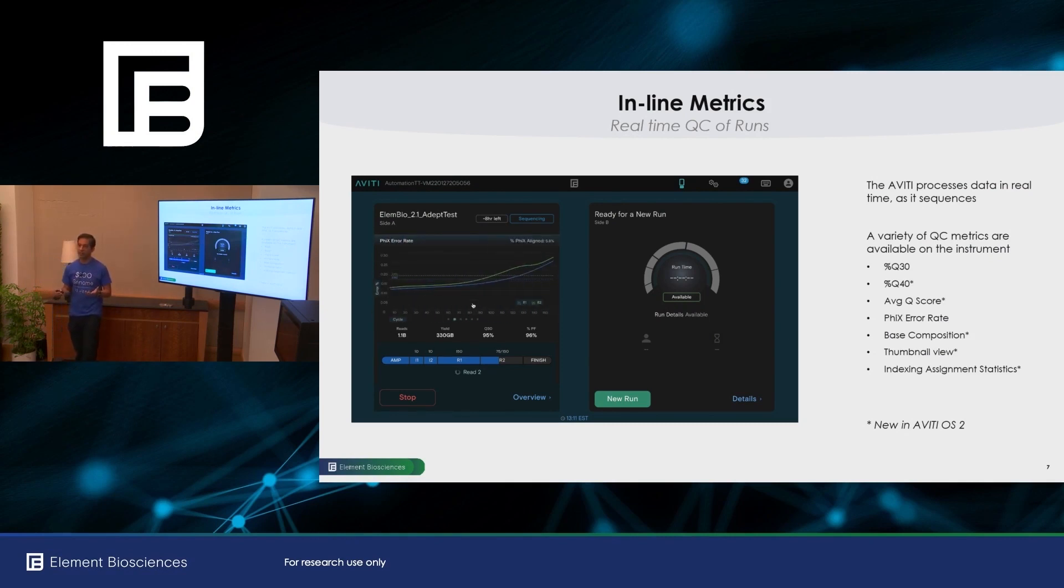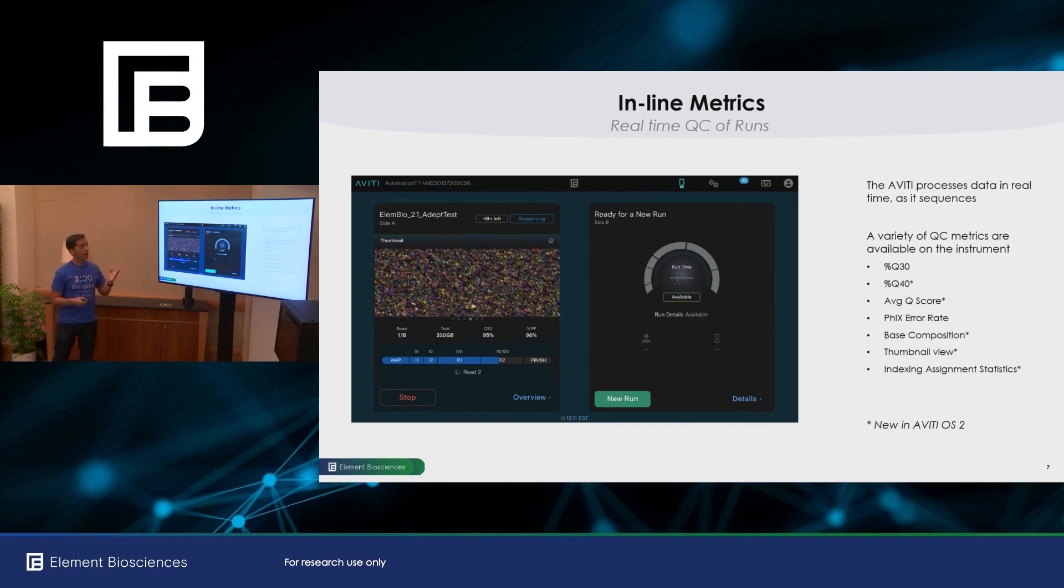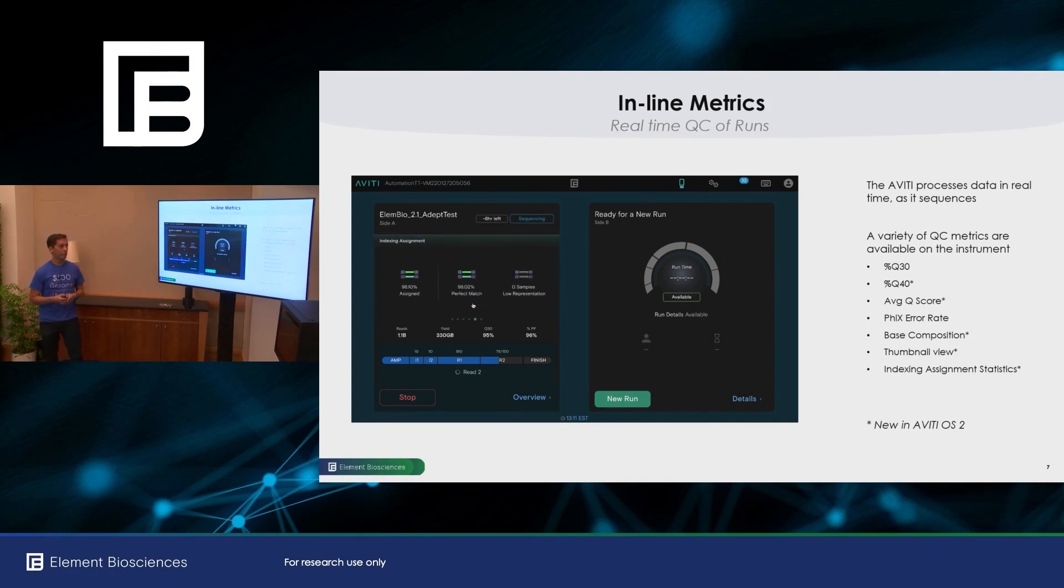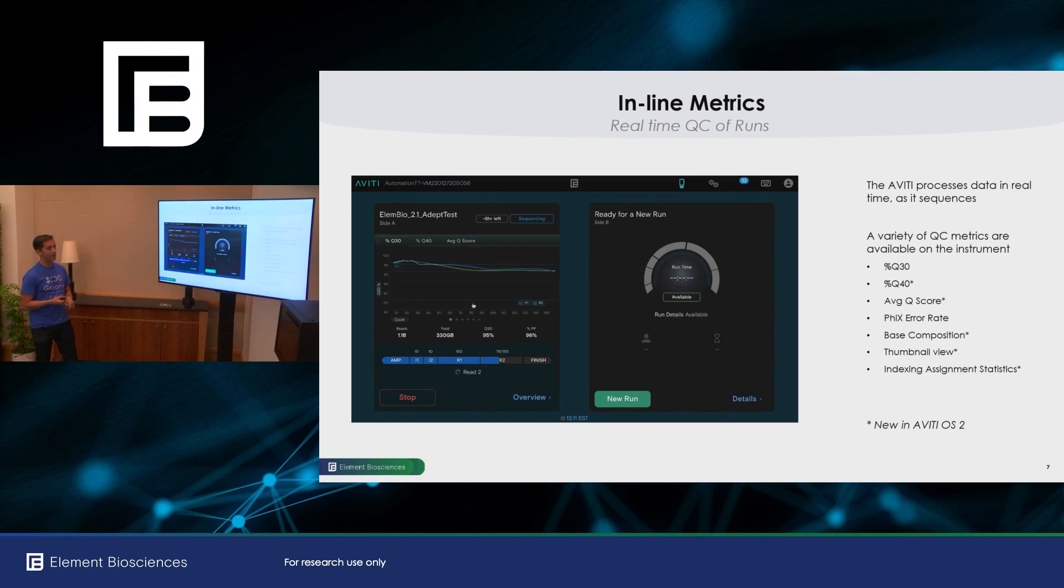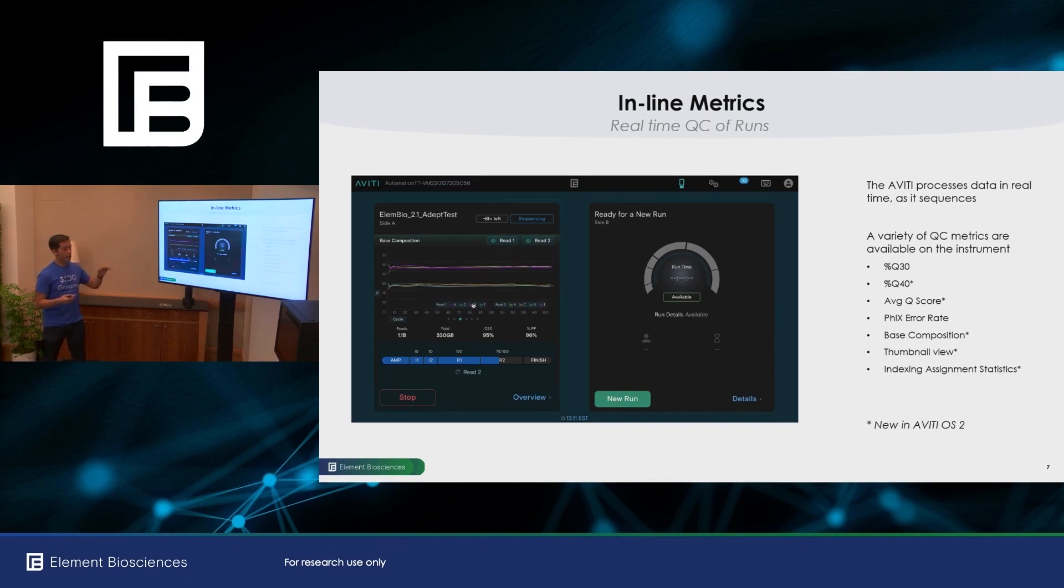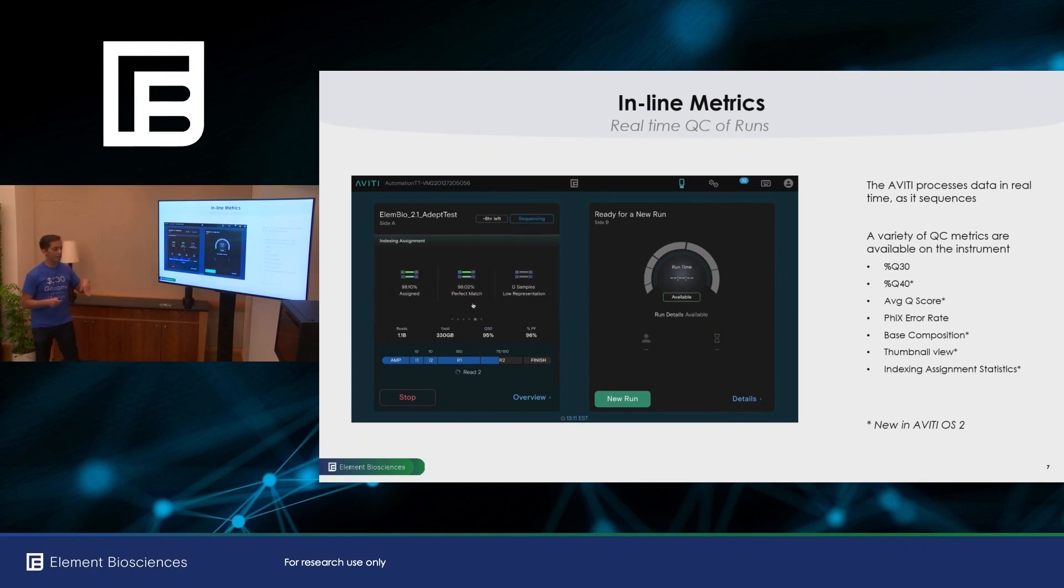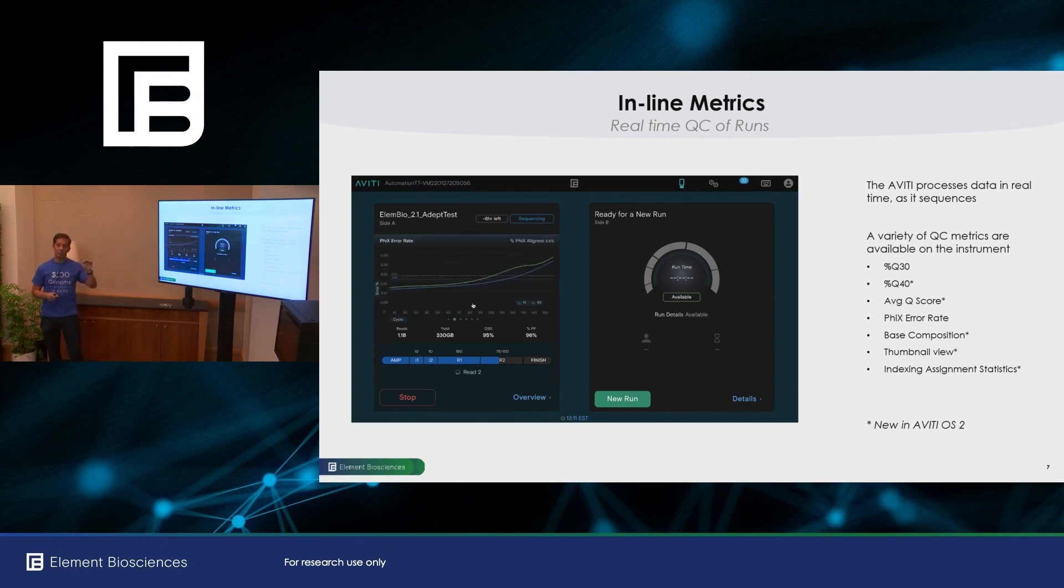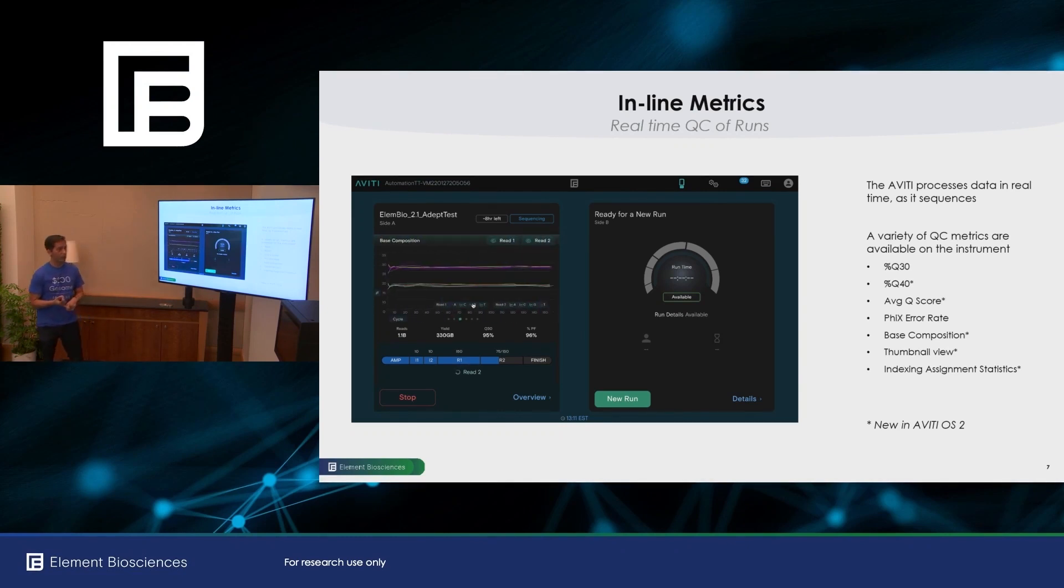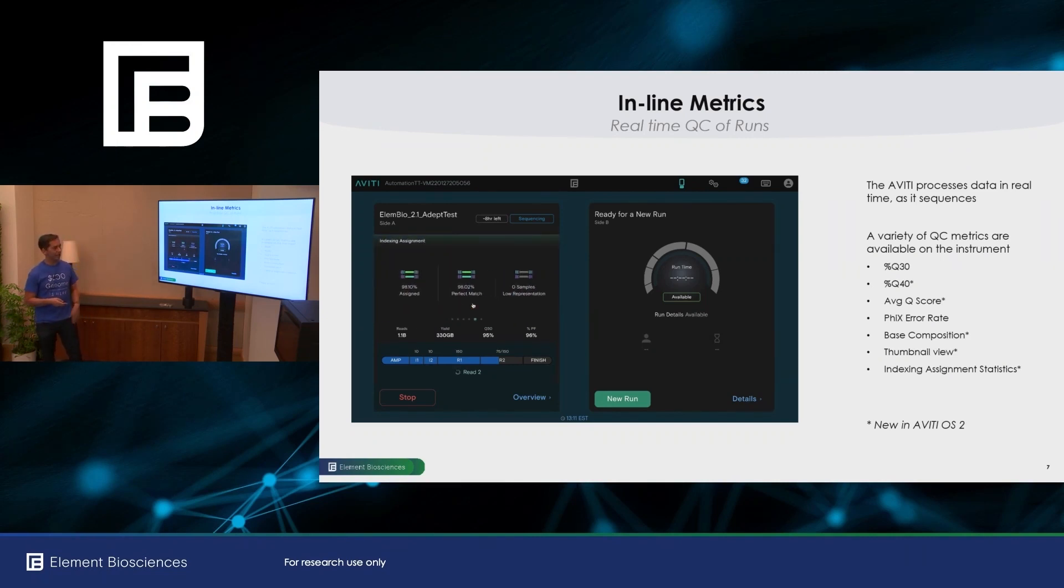And you're limited by the compute on the instrument, and then having to get all that data off. So as I mentioned, we have an FPGA on the system, and the primary analysis is done there. What that enables is that you have a real-time QC available on the instrument. So with Aviti OS 1.0, we had percent Q30 and Phi X error rate displayed. With Aviti OS 2.0, we'll be introducing many new metrics. Starting with 2.0, we'll be introducing indexing assignment statistics. And then didn't quite make it into 2.0. That's in validation right now. We're going to be adding a bunch of new features and new metrics in 2.1, including percent Q40, average Q score, the base composition, and the thumbnail view.